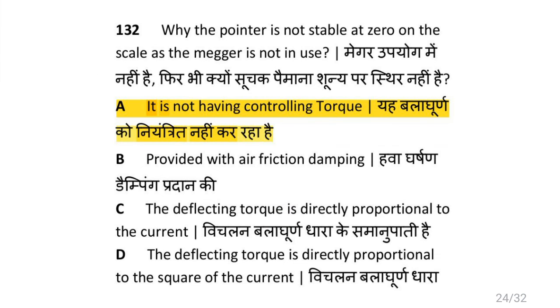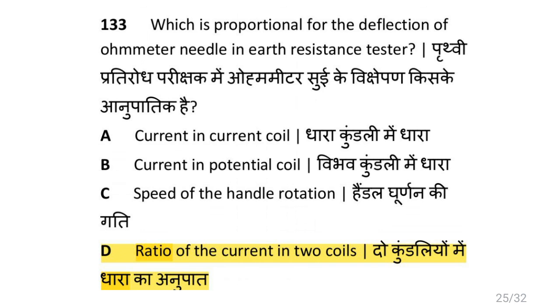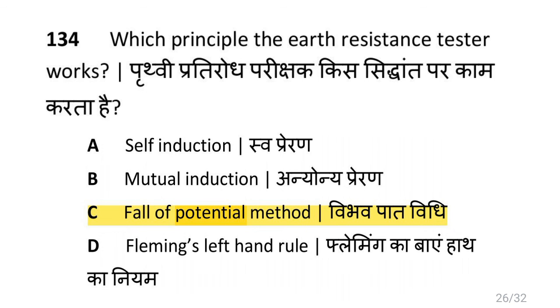Why is the pointer not stable at zero on the scale when megger is not in use? That is because it does not have controlling torque. Which is proportional to the deflection of the ohmmeter needle in earth resistance tester? That is the ratio of current in two coils. Which principle does the earth resistance tester work on? That is the fall of potential method.